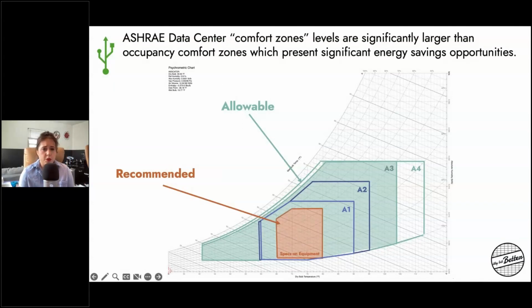Older equipment requires tighter controls, whereas newer equipment, and moving into the future, has higher tolerances, so you can increase the temperature even more. There's also another class called H1, which has an even higher requirement—those are for high density servers.